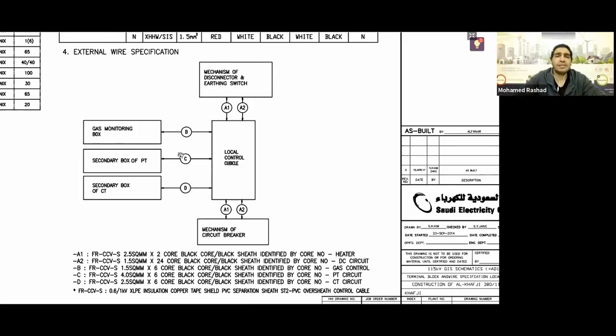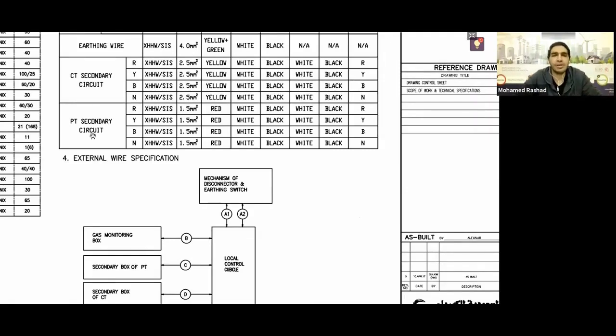Now, regarding the B, C, and D cables, P is the interface between my cell or my panel and the SF6 gas gauges, C with the VT circuits, and D with the CT circuits. Someone might say, the CT and VT you mentioned in your previous explanation, aren't they? The CT and VT, I'm talking to you about the internal wiring, meaning you are moving from one place to another within the same cell of yours. Something related to the CT circuits will use cables that are yellow with a white stripe and written on in black, and its cross-section is 2.5.